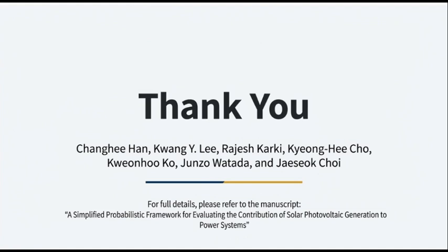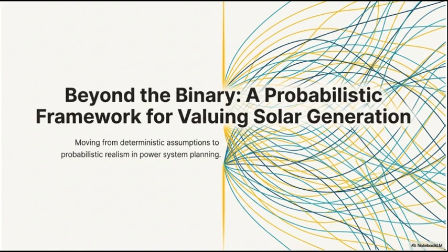So let's pivot to the PI-SOL framework. What is the fundamental mechanism that allows it to handle the uncertainty of all generators, conventional and solar, simultaneously? The backbone is a classic approach called the Booth-Baleriaux methodology, which operates within the effective load model, or ELM framework. This is pretty standard in probabilistic power system planning, specifically at what's called hierarchical level I. And hierarchical level I. That means it focuses on generation adequacy while simplifying the transmission network, for now. Exactly. It's a starting point.